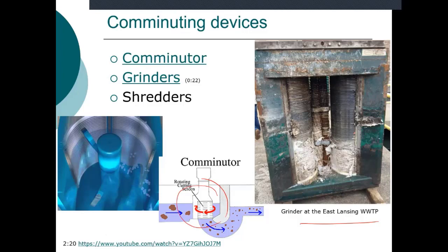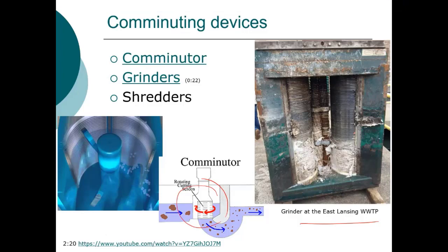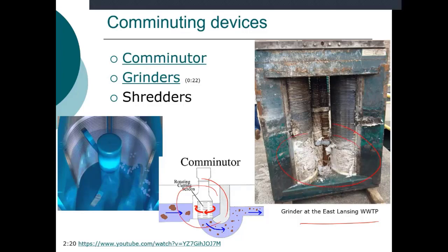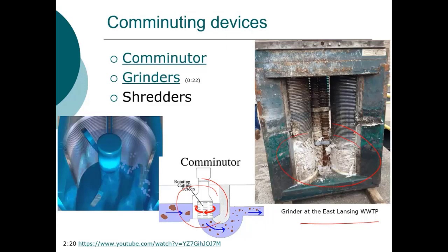And there's a number of things to observe in this. One, these are those flushable wipes that clog the grinder, they get stuck in it, and then somebody has to pull this out of the piping network and clean that device.